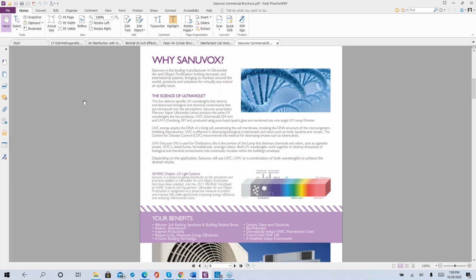Some give a shield to reflect the UV and intensify the focus downwards towards the A coil to also clean it. But UVC needs to shine a focused beam, yet bounce it around and reflect it off the sides of the duct to ensure that vaunted 99% kill rate claimed on first pass of Airstream. So Sanuvox and others mount the UV parallel with the Airstream.